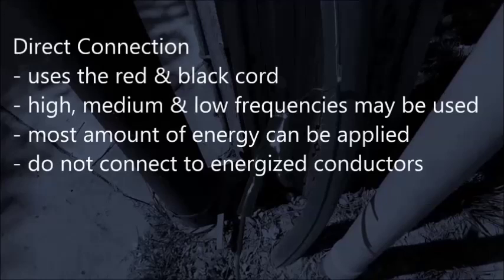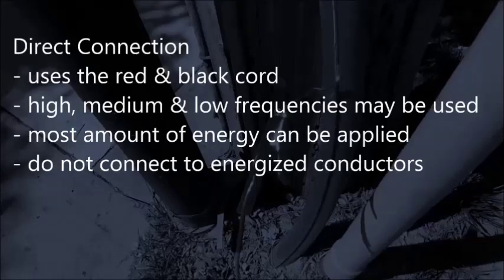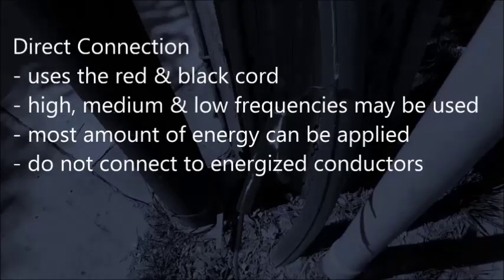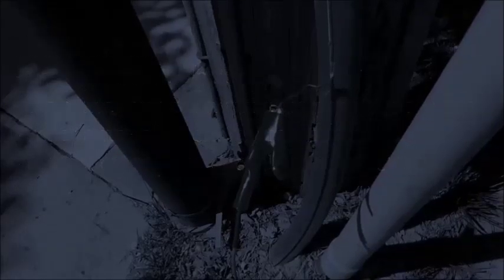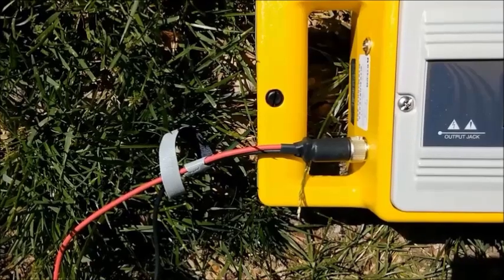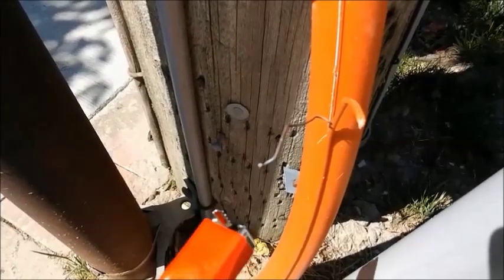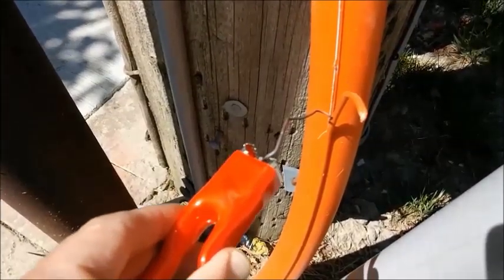Direct connection uses the red and black cord to directly conduct the locate frequency to a utility. All frequencies may be used in direct connection. To perform a direct connection, plug the red and black cord into the output jack of the transmitter. Connect the red clip to a conductive part of the target utility.